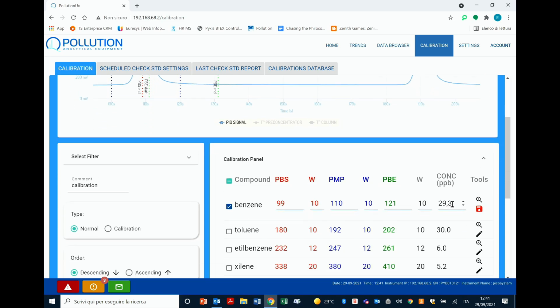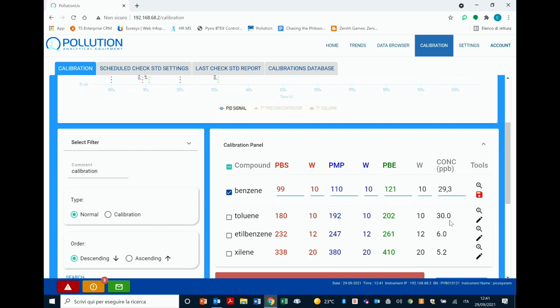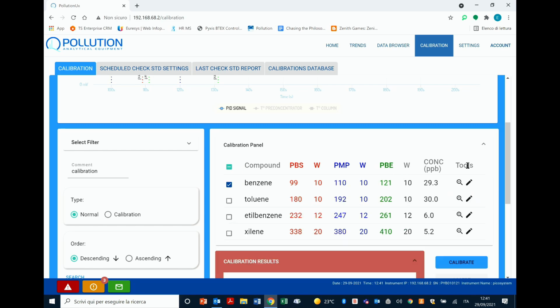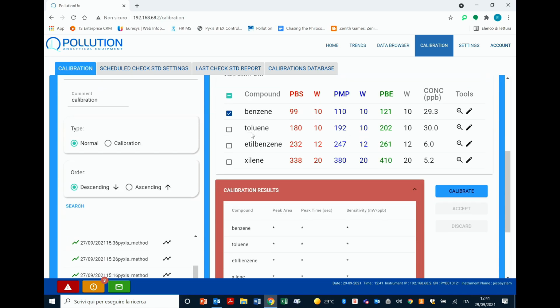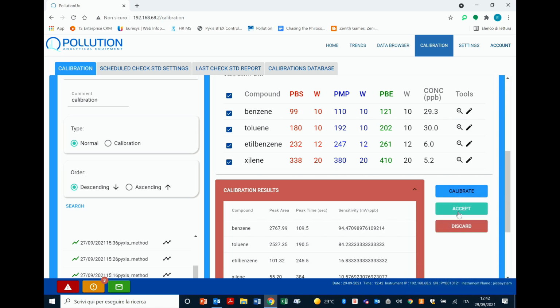In the end, you will put the concentration in ppb that you know is coming from the certified gas tank. So as I said before, we usually put for the low concentrations around 30 ppb of the benzene. When this is done, you can save, and you can do this for all the 4 different compounds. If you then put all compounds selected, you can then press calibrate.